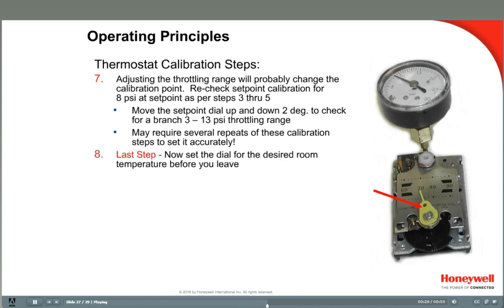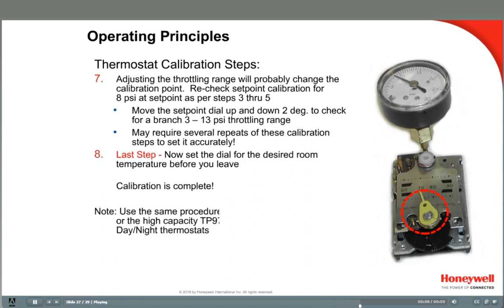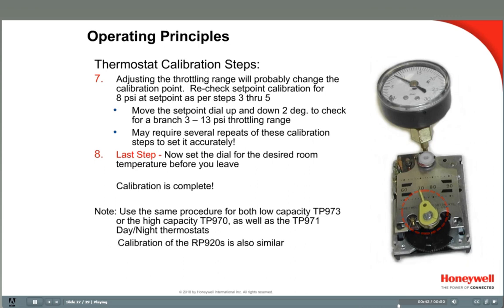The thermostat is now calibrated. Be sure to set the set point dial to the desired set point before leaving the room — remember, right now it is set at the ambient room temperature used for calibration, and that may not be the desired room temperature. You'll use the same procedures to calibrate other models of thermostats, and in fact the procedure for calibrating the RP920A is surprisingly similar to the TP970.